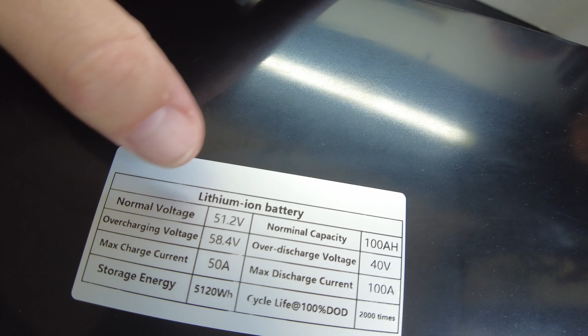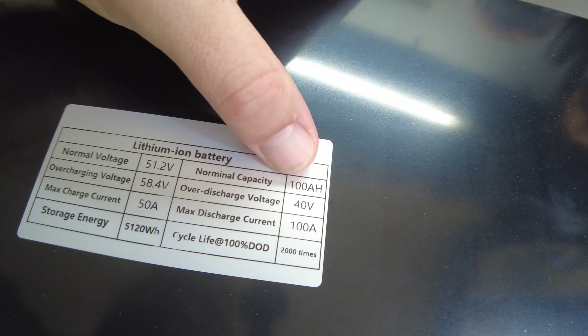All right, so let's look at the stickers on the battery here. It says normal voltage is 51.2, overcharge voltage is 58.4. It says nominal capacity is 100 amp hours. Over discharge voltage is 40. Max discharge current is 100 amps. Cycle life at 100% depth of discharge is 2,000 times. The storage energy is 5,120 watt-hours, and the maximum charge current is 50 amps.